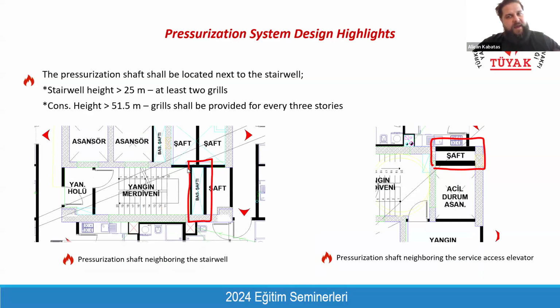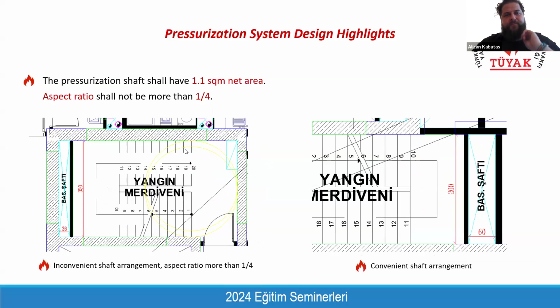should be fire rated. That's why if you are designing a high-rise building and if your building needs a pressurization shaft, it should be designed at the beginning of the project. Otherwise, finding a place for that 1 square meter shaft will be a huge problem during your core design. You need to take space from other shafts or technical rooms, or you need to enlarge the core, which will not make the investor happy.